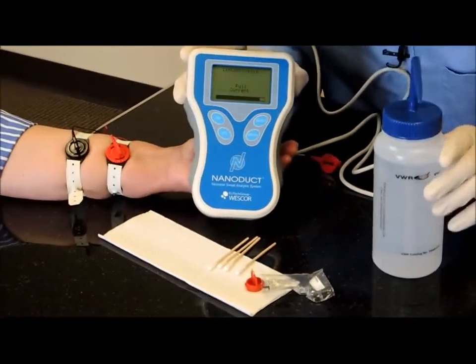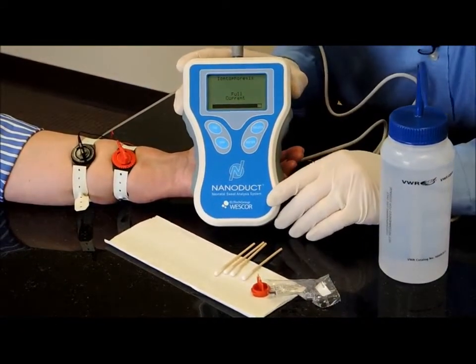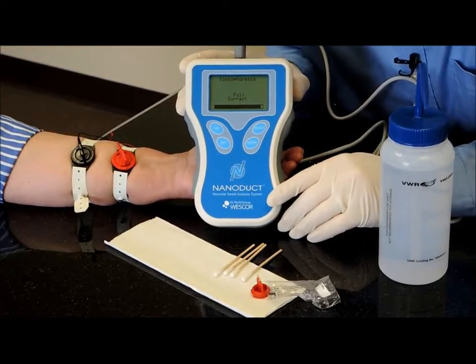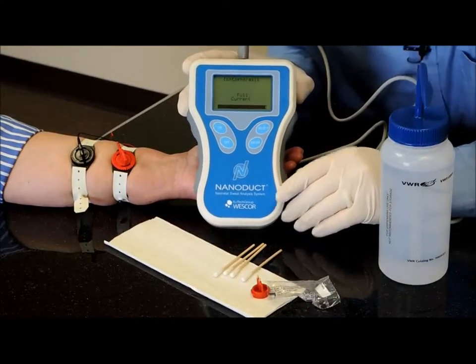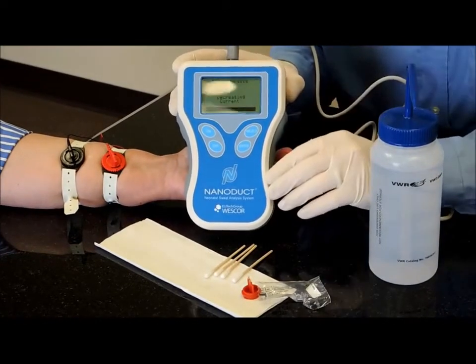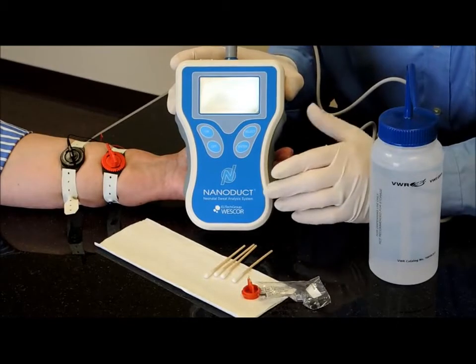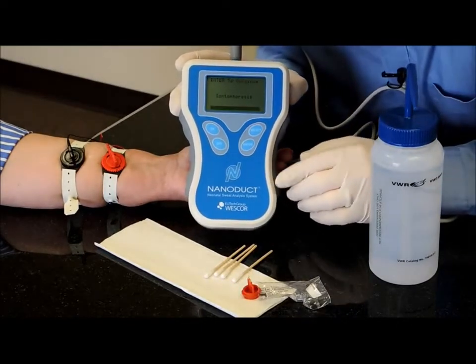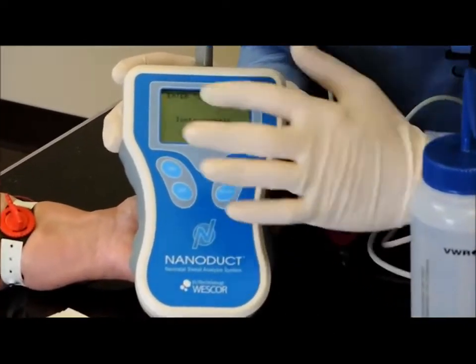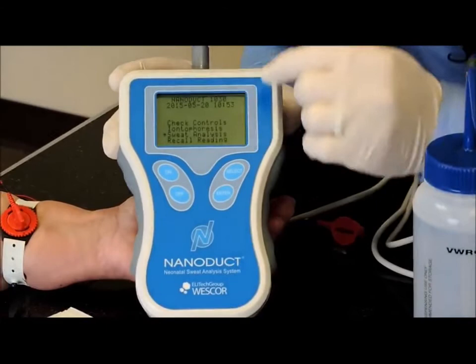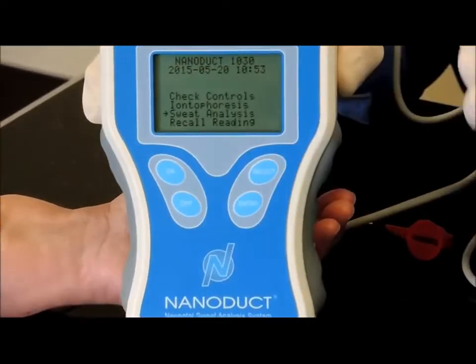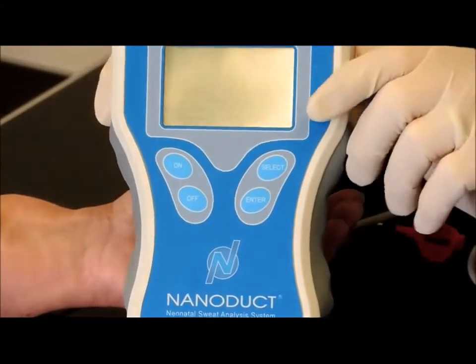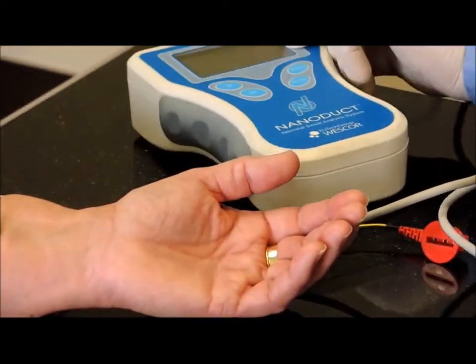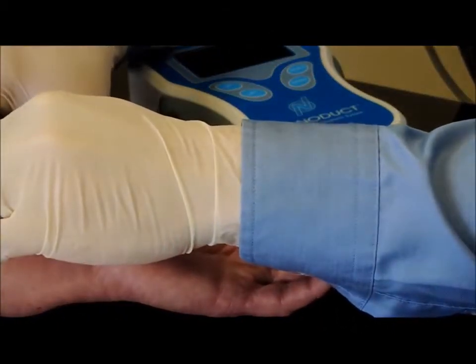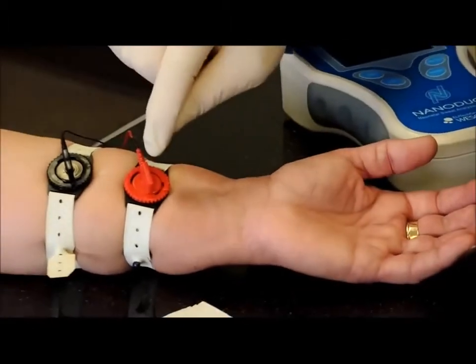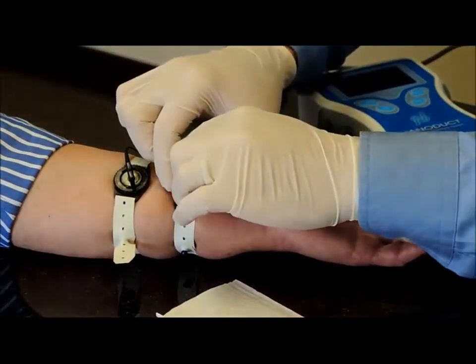You can see the iontophoresis progress bar is almost complete. And at completion, it will say decreasing current, and then you'll go back to the main screen. Okay, so it says iontophoresis complete. Press enter to continue. So I press enter, and now we're back at the main screen with the arrow pointing towards the sweat test. So at this point now I'll put the Nanoduct down, and I'll remove the red electrode, only the red electrode. Keep the black there.